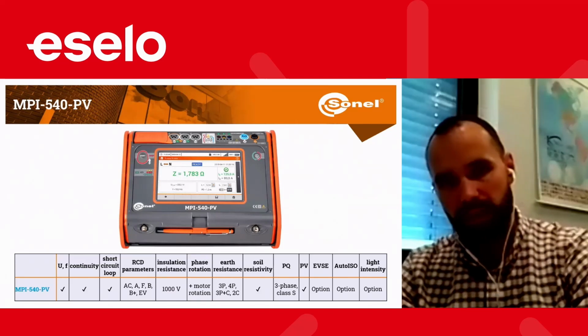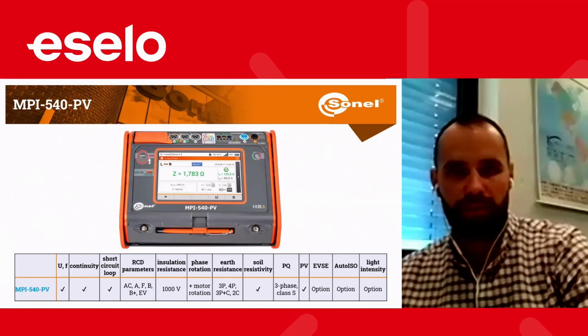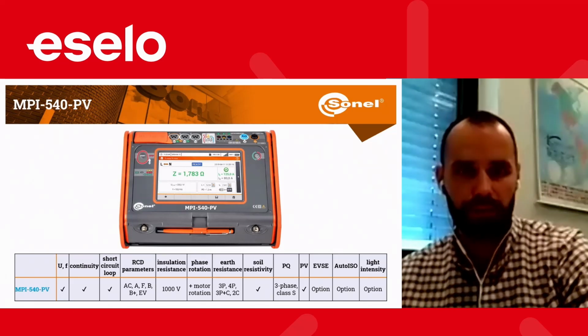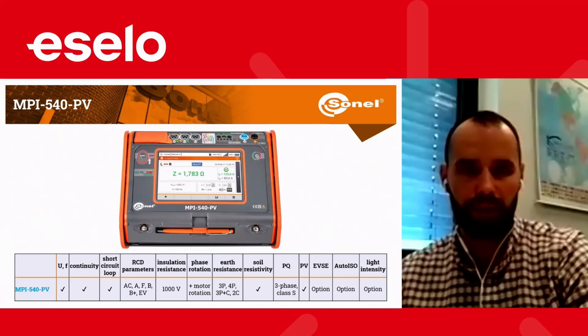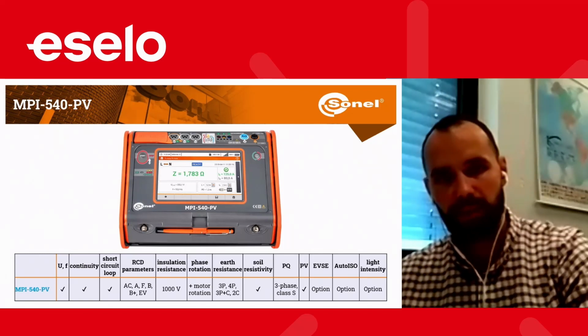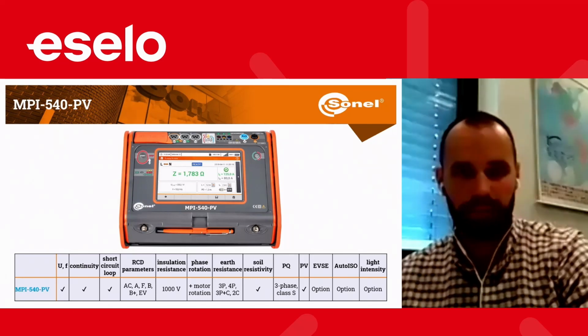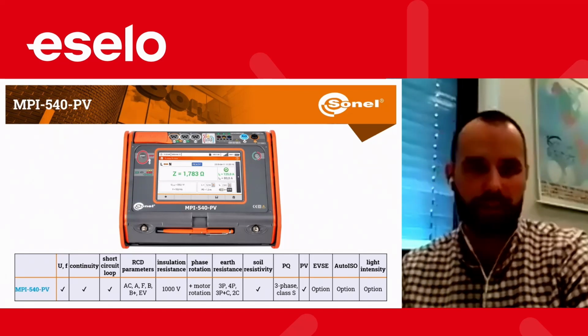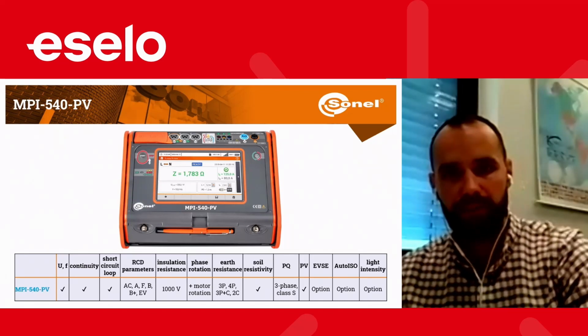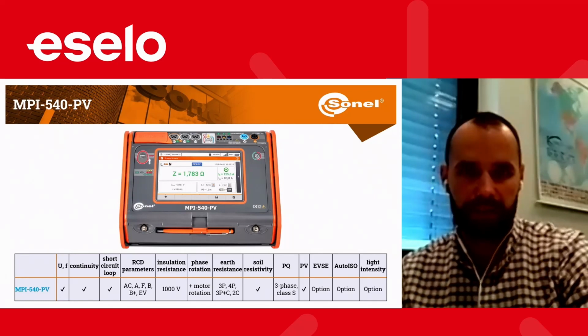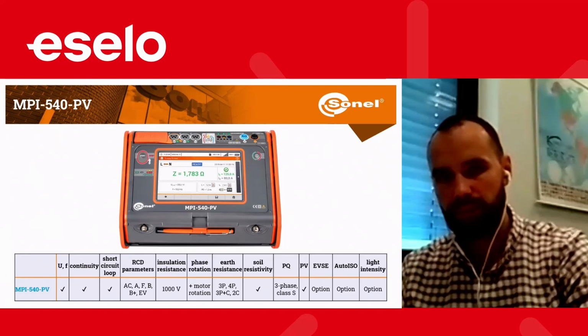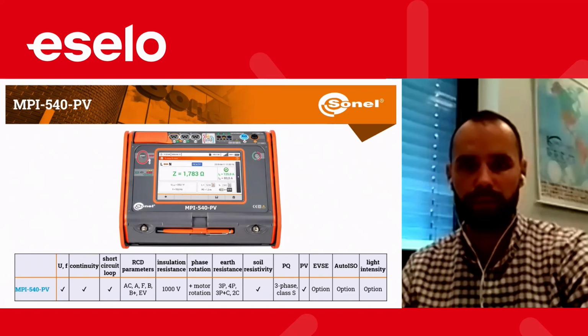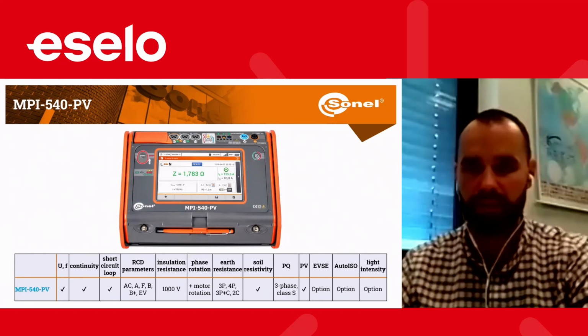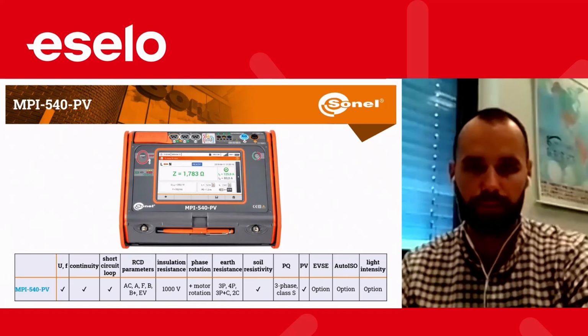And also the MPI allows you to make the measurements of voltage, frequency, continuity, short circuit of the loop, which is important on the AC side, RCD parameters AC, A, F, B, B+, and EV, insulation test up to 1000 volts, phase rotation, earth resistance, which is also important, especially in hard soil conditions, where we have to make the measurements with a different type of method.